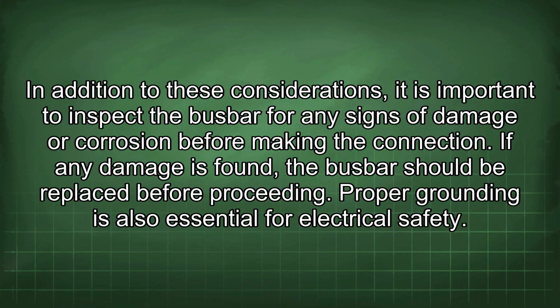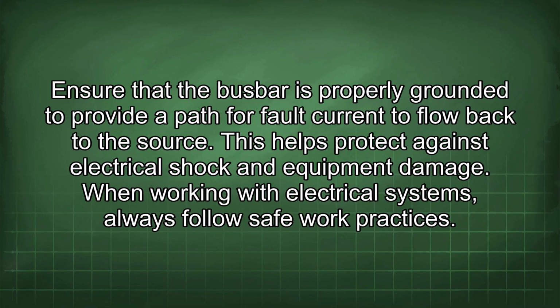In addition to these considerations, it is important to inspect the busbar for any signs of damage or corrosion before making the connection. If any damage is found, the busbar should be replaced before proceeding. Proper grounding is also essential for electrical safety. Ensure that the busbar is properly grounded to provide a path for fault current to flow back to the source. This helps protect against electrical shock and equipment damage.